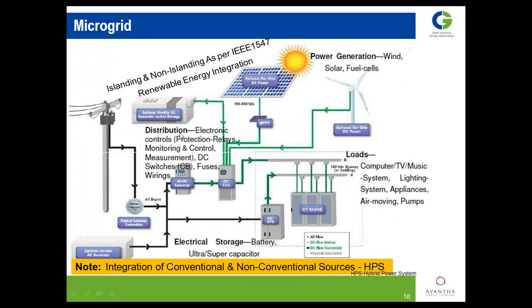So it applies to the distribution, the storage, the load, and the generation. Will it be an islanding type or a non-islanding type as per IEEE 1547? How will that integration happen, and how can I get a better microgrid system as per my need and requirement, viewed as a hybrid power system? That's an important area today, and it helps a lot towards the T&D losses of my system. It gives localized power improvement in view of unbalancing or peak power control, and all that gets managed and mitigated. A hybrid power system is an important area for utilities today.